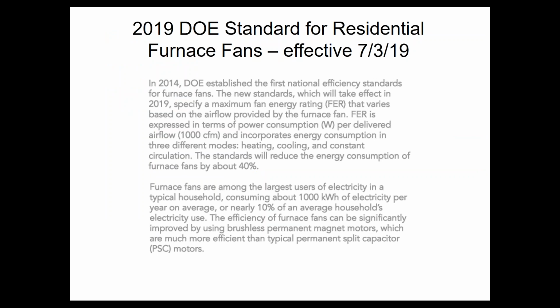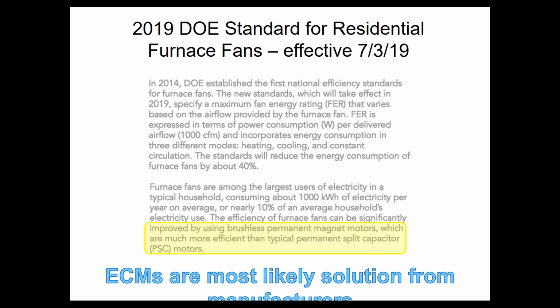This is going to become very easy to comply with very soon, because some of you might have heard there's a Department of Energy rule that has been published. It goes into effect in 13 months. That'll essentially make an ECM motor the bare legal minimum thing that you could buy. There's a new thing called Fan Energy Rating, FER, that'll specify the minimum efficiency of motors and fans for residential equipment like furnaces. And because of that, a standard PSC motor will not be able to comply. And the manufacturers, I presume, will use ECMs, or they'll invent some new technology. So probably ECM. So that's going to kind of go away on its own.